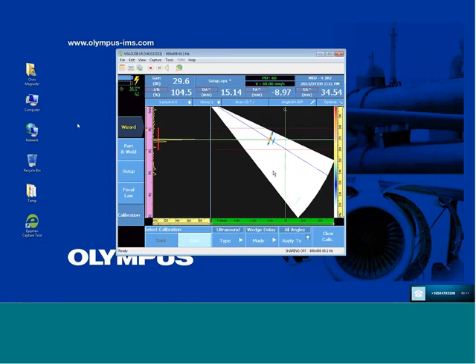So we also have new in the software under Preferences, Instrument, and Screen, a calibration function that allows us to calibrate the touch screen. That will walk us through a quick procedure of only 1 or 2 minutes maximum that will make the touch screen's calibration to your finger and finger position much more accurate.